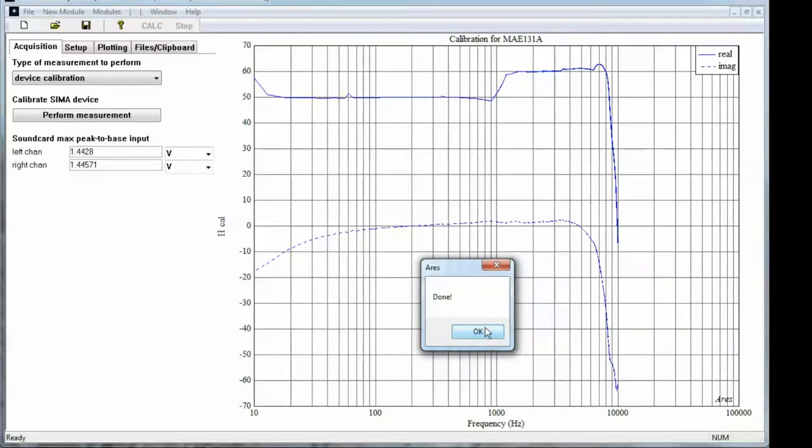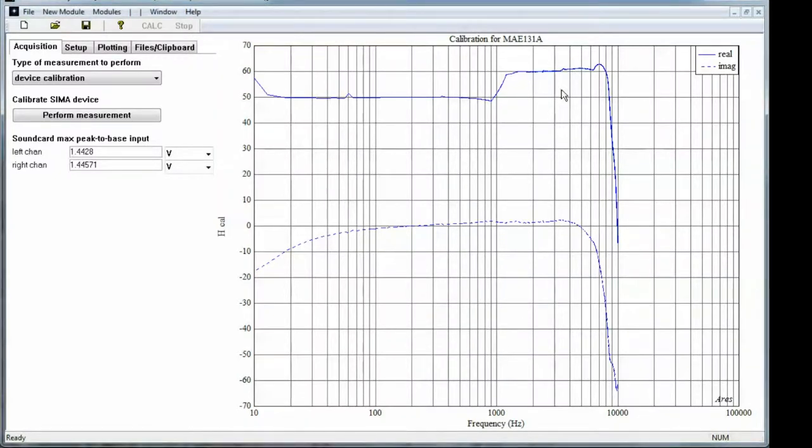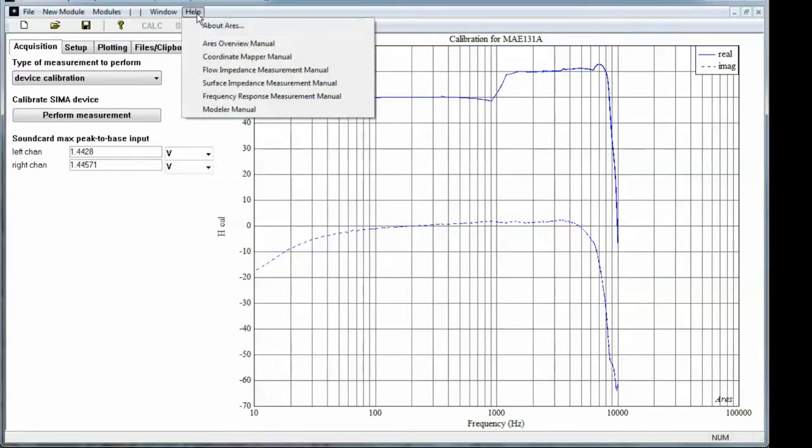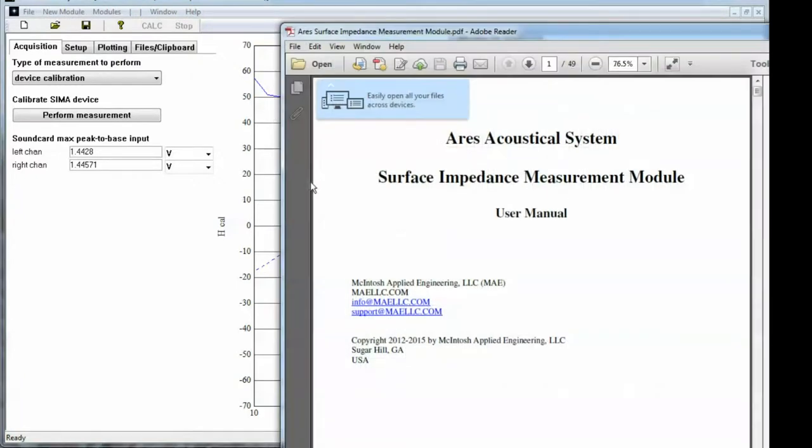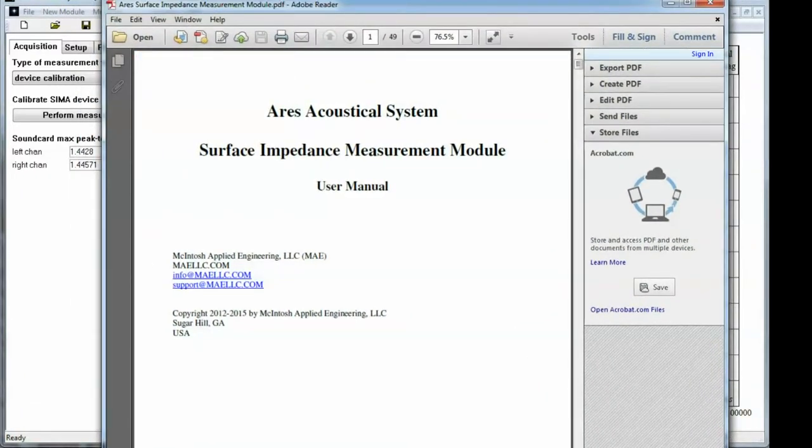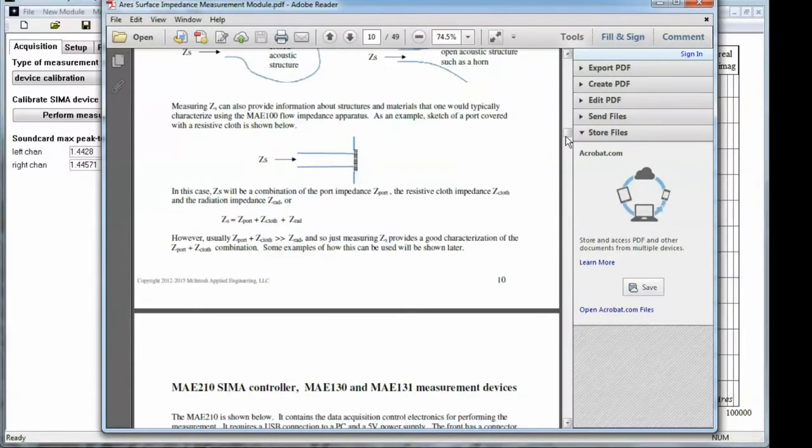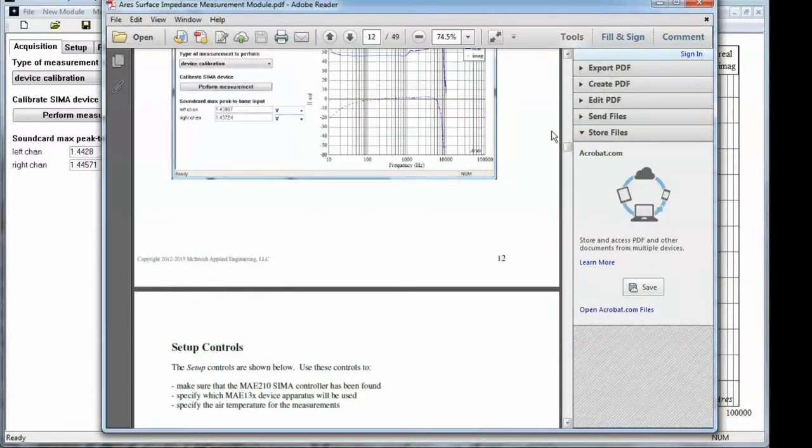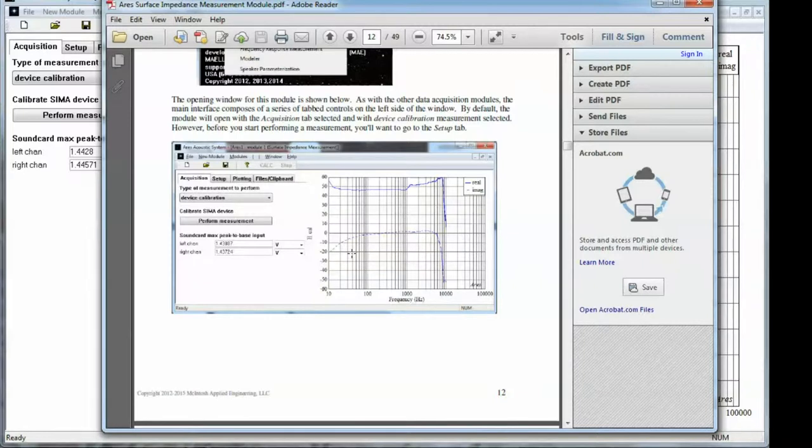So when the measurement is done, the dialog box will pop up indicating it's completed calibration procedure. And you will see a calibration graph in the main Ares window and it will update the sound card's maximum peak to base input level. What I'd recommend is, while you're getting used to using these devices, check that the calibration curve is somewhat close to what's in the manual for the SIMA module. To pull the manual up, you can go to the Help menu, select Surface Impedance Measurement Manual. It will find it on your system and we can page through here until we see a calibration curve. Here's a calibration curve for the 131 and they look similar and the levels are about right. So we're fine with that.